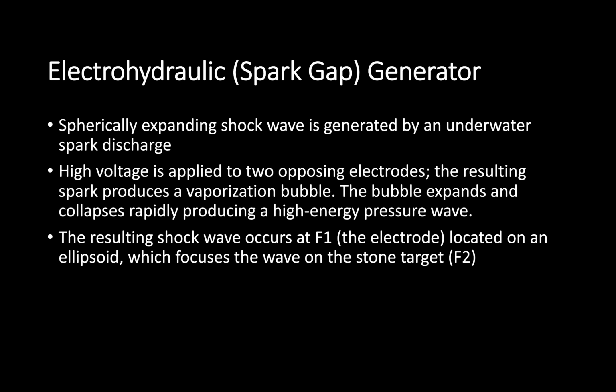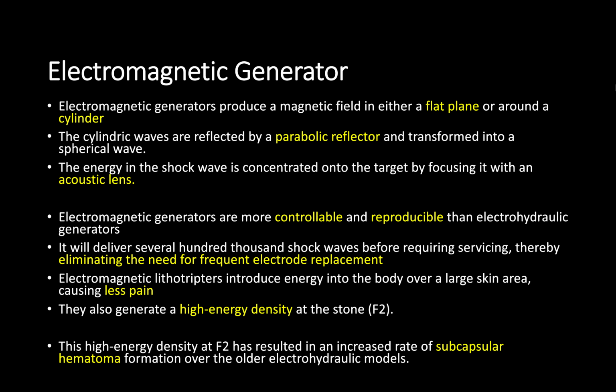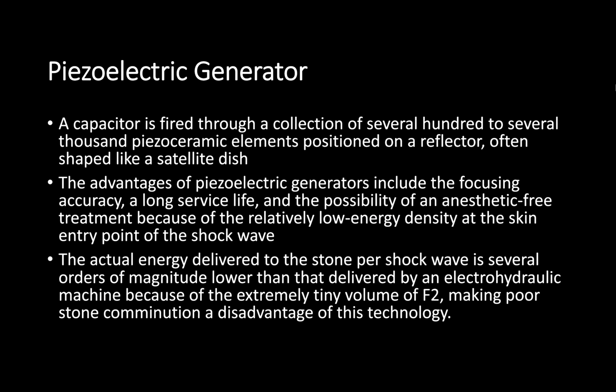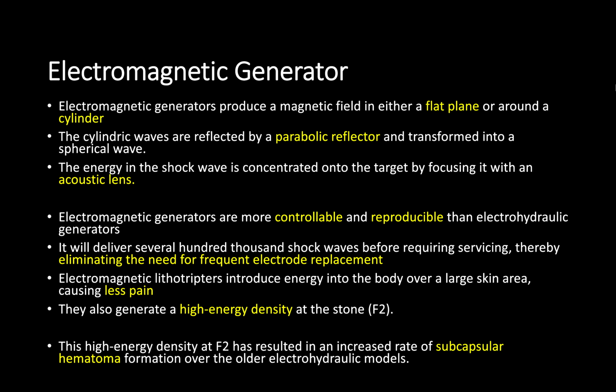The piezoelectric lithotripsy works through the semispherical arrangements of piezoelectric crystals. These have an electrical current applied to them. They expand and contract, producing ultrasound waves, and their semispherical arrangement then helps to focus the waves onto the target. And then finally, there's the electromagnetic lithotripsy, which is the most commonly used in everyday practice. In this, the electrical current is applied to a cylinder, producing cylindrical waves. These are then reflected by a parabolic reflector to produce spherical waves. These are passed through an acoustic lens, which is the mechanism by which the shockwave is then focused onto the target of the stone.